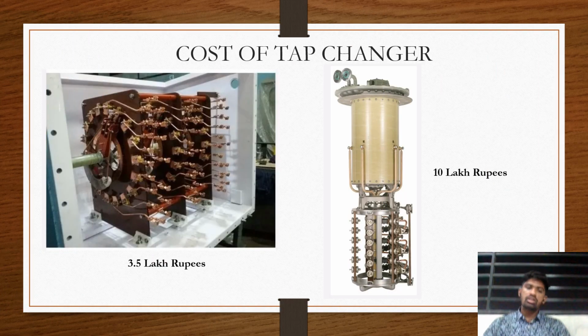The cost of a tap changer could vary from 3.5 lakh to 10 lakh rupees. This variation depends upon the number of taps present, and it also depends upon whether you have a diverter unit or not. With a diverter unit, the cost of the tap changer will definitely increase. Without a diverter unit, you might get it for around 3.5 lakh.